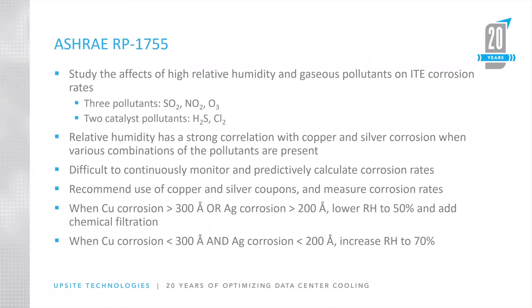Because of the different permutations of catalysts, pollutants, relative humidity levels, etc., it's very difficult to set up continuous monitoring and predictive models to determine what your corrosion rates may be. So the recommendation — the update to the thermal guidelines — is that if you suspect you may have any of these pollutants present in your area, you should install copper and silver coupons in the facility and measure the corrosion rates.